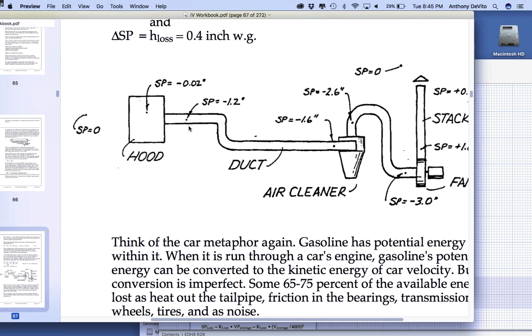So that number that we need to make this hood right is something that we're going to get from the ACGIH standards. They have a book, a manual that they republish every year, with all different kinds of hoods and what the performance has to be of the hoods, what formulas you can use to calculate those values. So either by using their calculations or the manufacturer's spec, you determine that has to be negative 1.2 inches, right? That's not anything you can do for yourself. You could do it experimentally if you wanted to, but usually you're getting that information either by calculation from the ACGIH book that describes each hood, and I'll bring a copy in next time, or from the manufacturer's specs. So that's what you need. You need that much pressure.